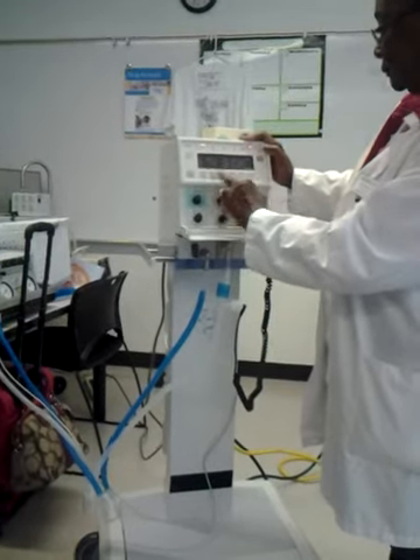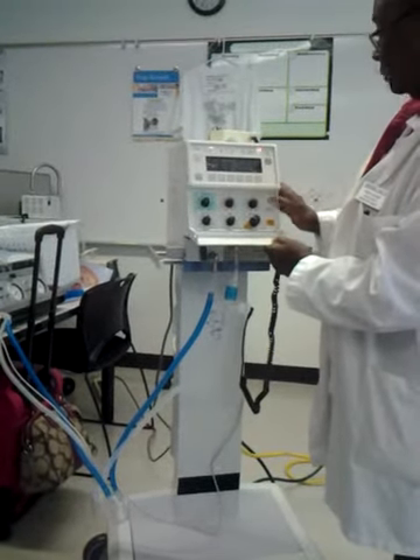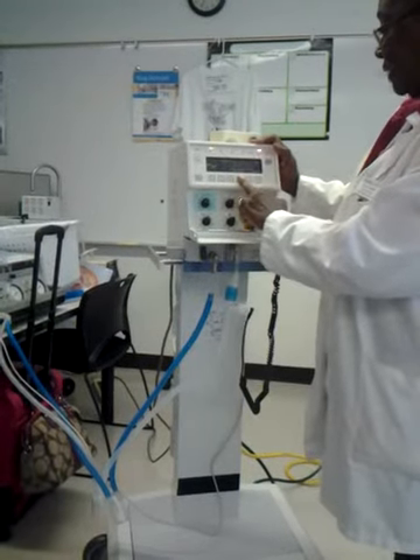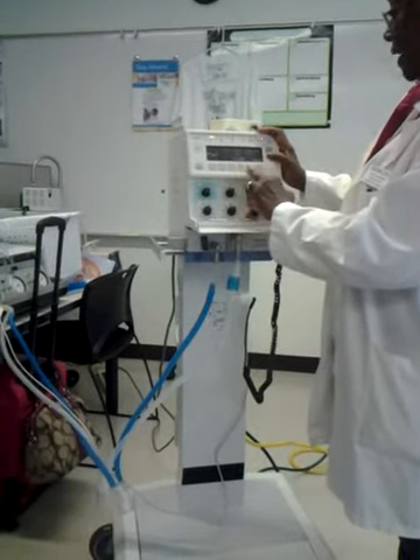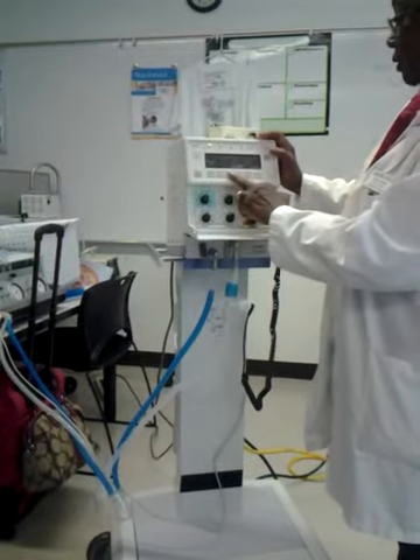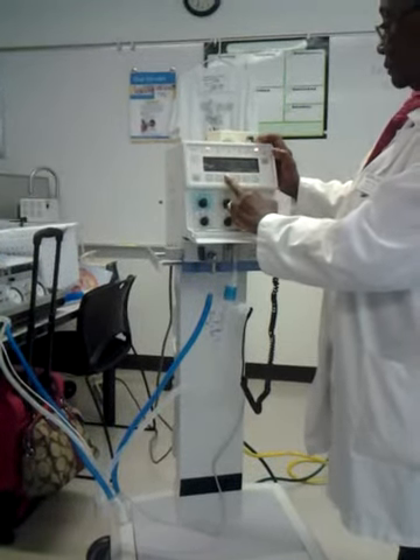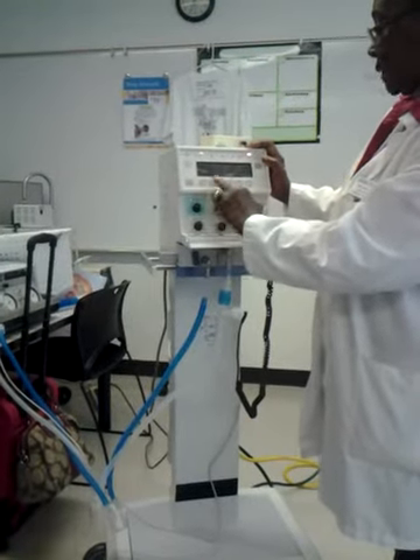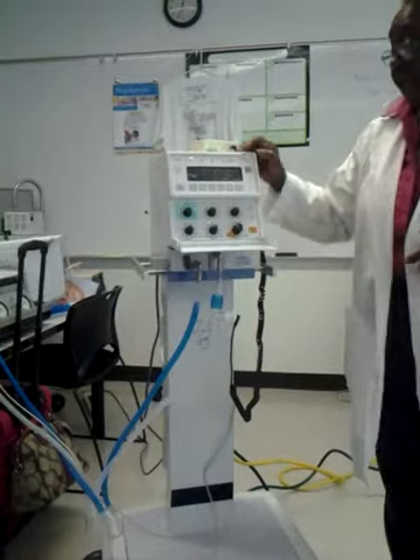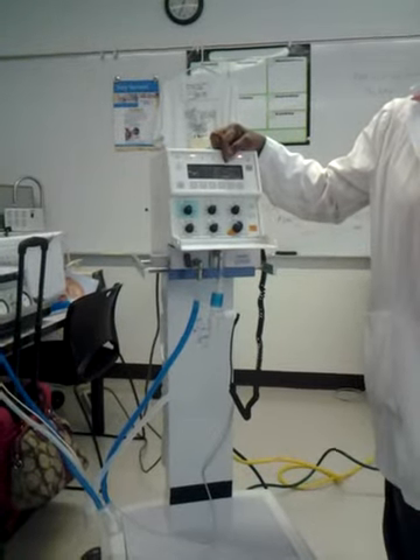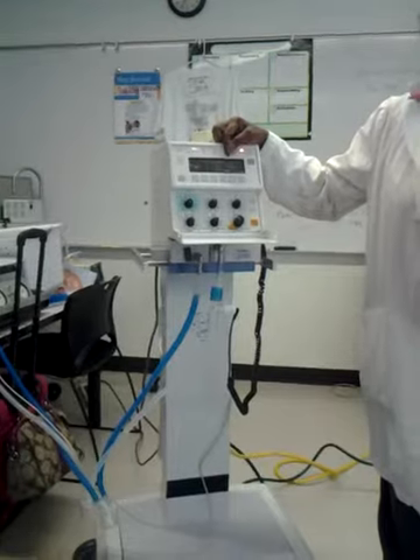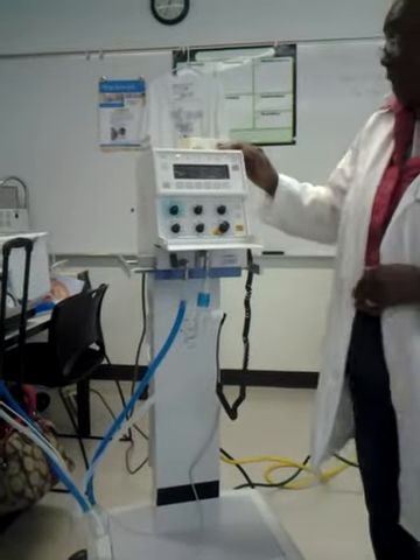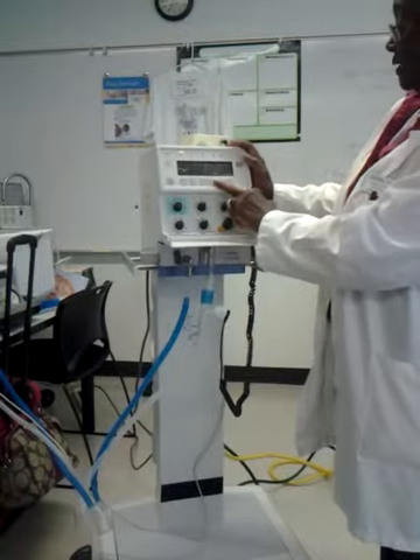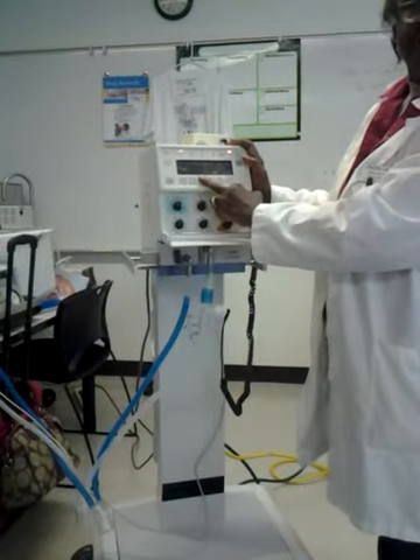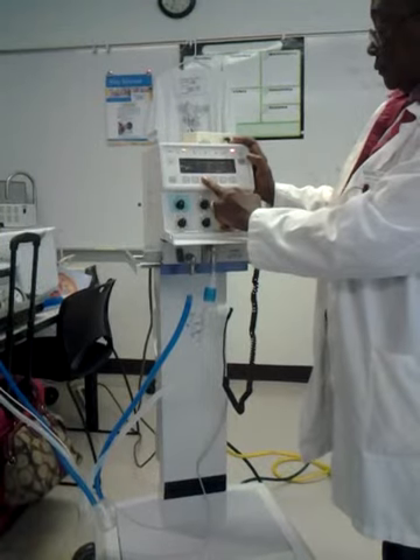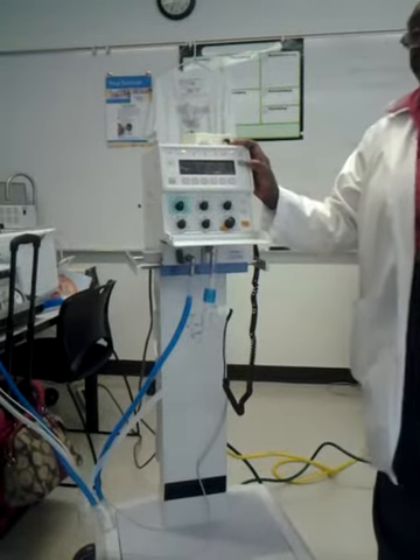Let's see if we can go back. You can also go into SIMV. I'm in assist control mode. When I hit assist control, I have to say on to let it know it's on. I have to change my trigger level. I can go into volume guaranteed, and when I go into volume guaranteed, I have to set the volume that I want the baby to be guaranteed to get, even though I'm doing pressure ventilation. And you're going to set that by hitting the plus and minus key, and that will change your volume. And the doctor would give you that value as well? The doctor would give you that value.